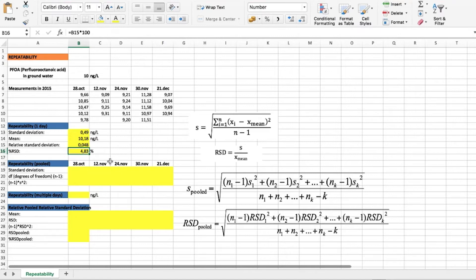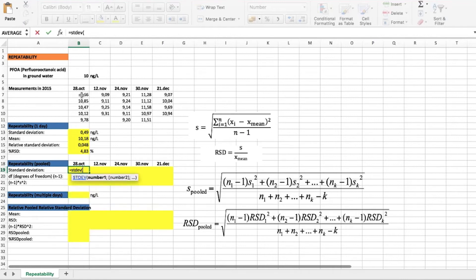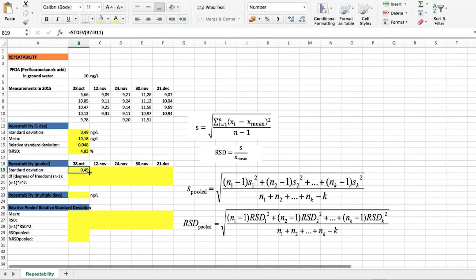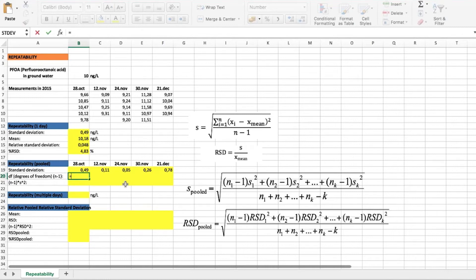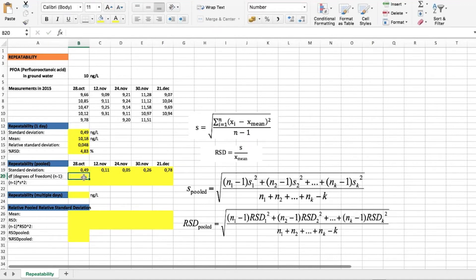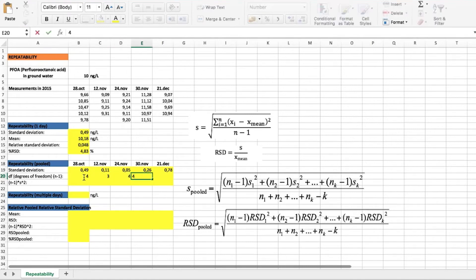However, this result gives us the repeatability of a single day. To get a better idea of overall repeatability, it is useful to use pooled repeatability, which we can calculate using this formula here. We first find the standard deviation of the measurements done on each day, and then we need degrees of freedom — which is the number of measurements minus one: four when we have five measurements, or three when we have four measurements.